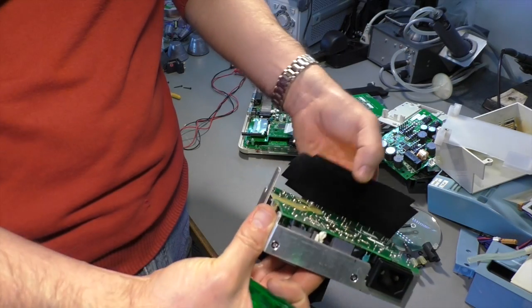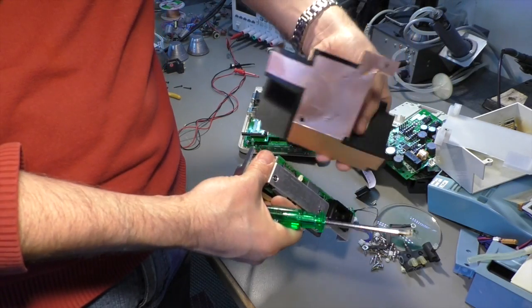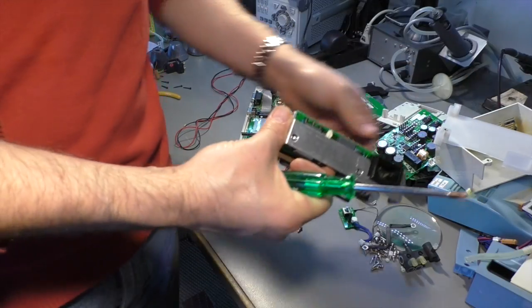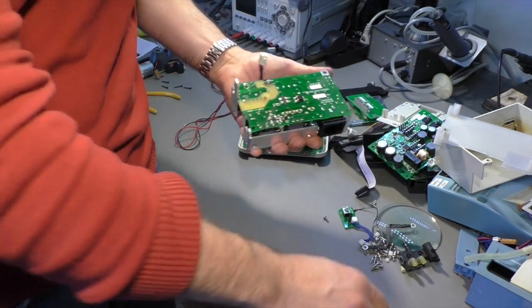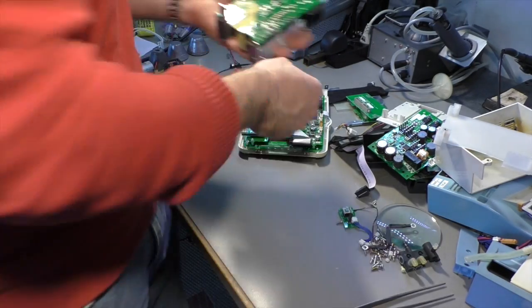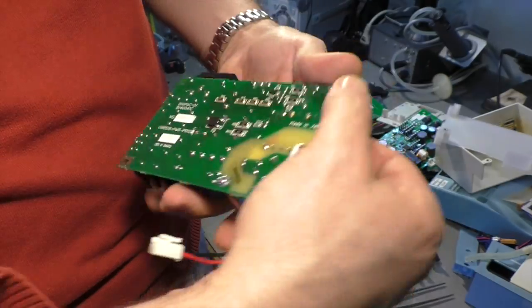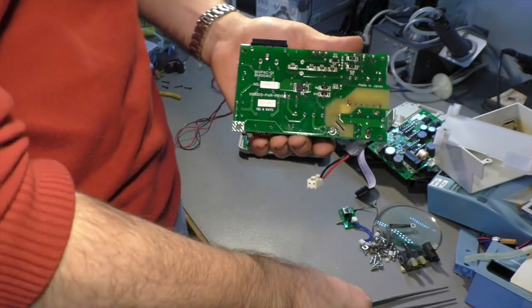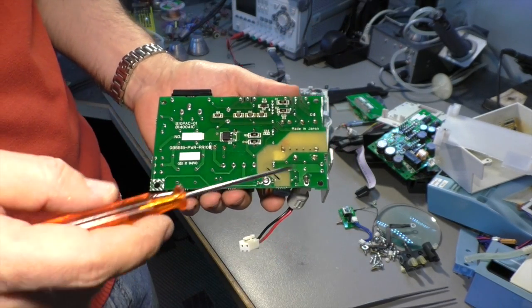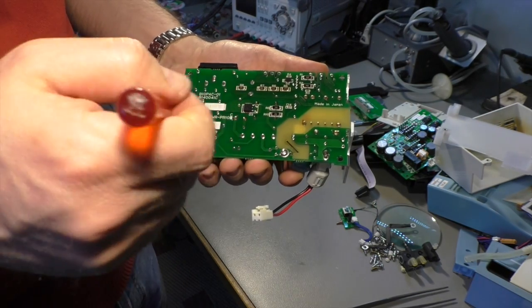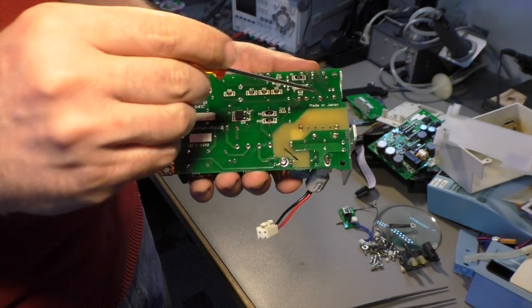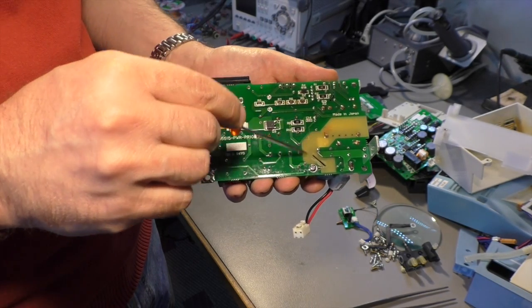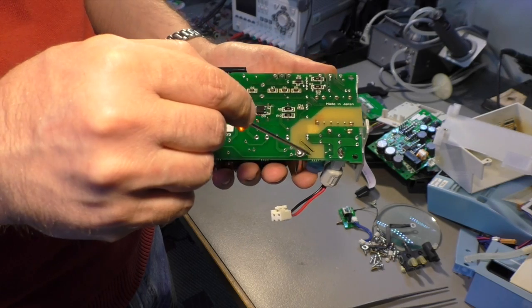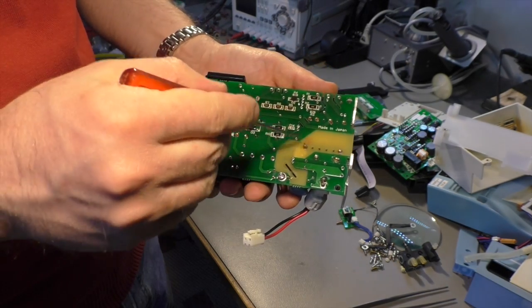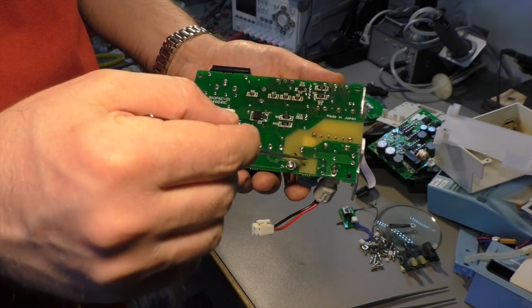Okay, that's the plastic base insulation, then again shielding and insulation all around the power supply. Insulation is a very important thing, because this is a medical device, and medical power supplies are regulated, constantly checked, and have to be safe in any way, because there is a human being directly connected to this unit, so you must avoid any leakage currents from the mains to the low voltage side.